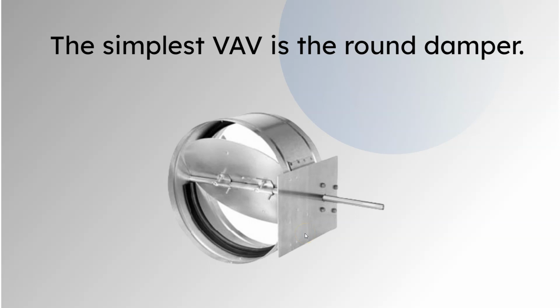This is the very simplest form of a VAV. It's literally a round damper with a shaft coming out the side. That's where you're going to mount the controller or actuator. And that controller or actuator is going to turn that damper inside that round duct. Obviously, this is going to be attached to ductwork. You're going to have an air handler on one side pushing air towards the VAV. And on the outside, you're going to have a diffuser in the ceiling. You look up at the ceilings every day, those are diffusers. So as this damper opens, obviously more air goes through. As it closes, less air goes through.